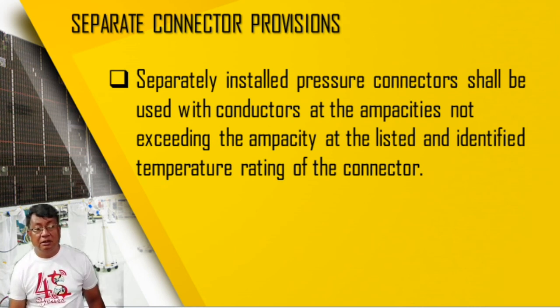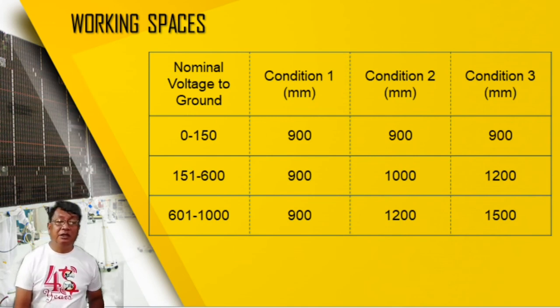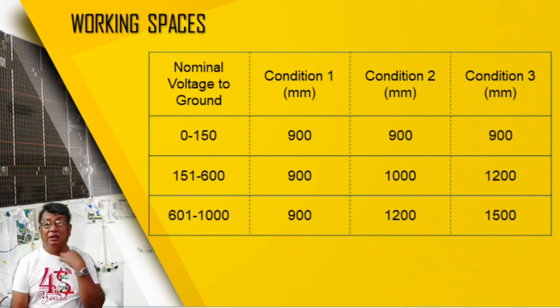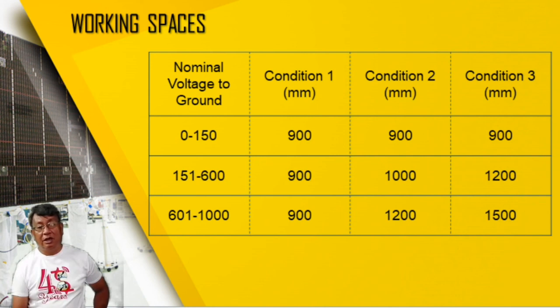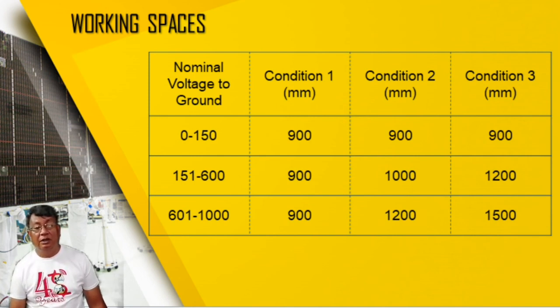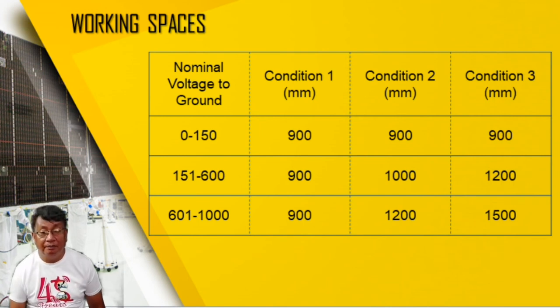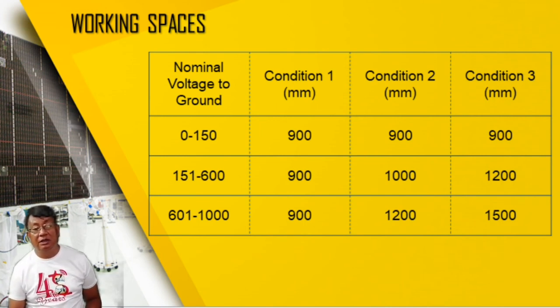Okay, we have next the workspaces, no? This is in millimeters. So nominal voltage to ground. When we say, for example, 220 volts, that is in between 151 volts to 600 volts. We have these values 900, 1000, 1200. So that is the workspaces specified.